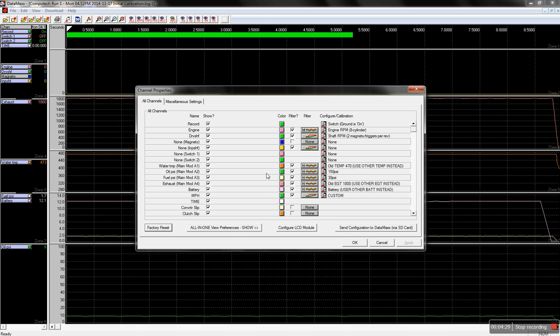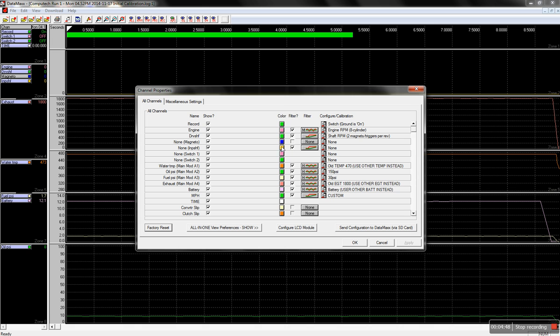Okay, so now here's where the important calibration information happens. In main module analog 1, the default is that it is indeed for water temp. If we take a look at our configuration, we do in fact have water temp installed in A1. But our sensor type is going to be the DATCON. It's the one-wire sensor. And in the calibration currently, it has got one of the different sensors. So we're going to change that calibration.